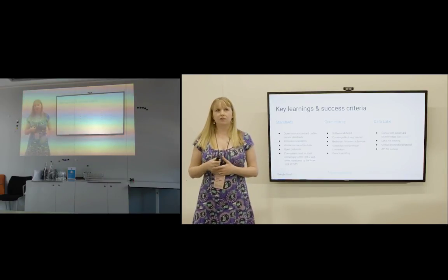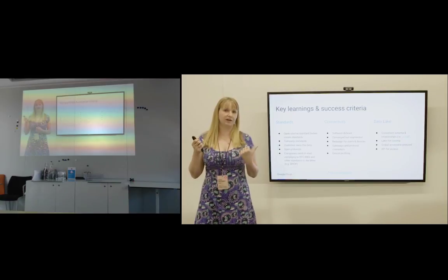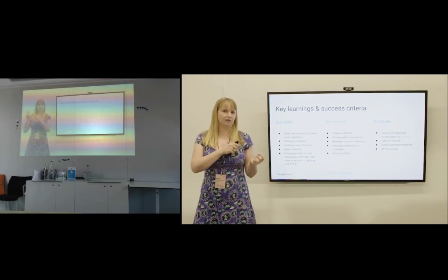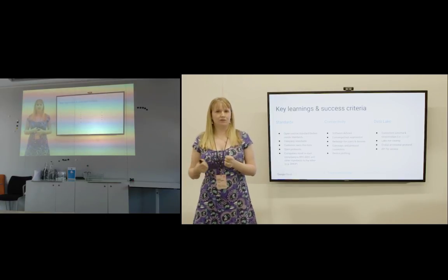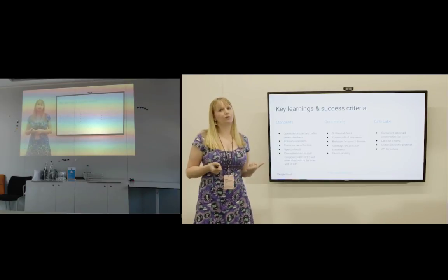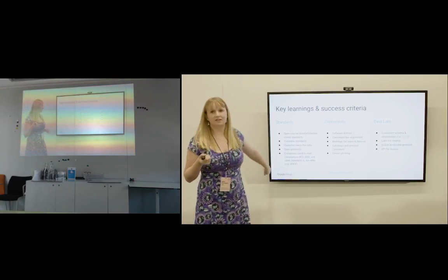And one for the device manufacturers. A lot of these devices are used to having really unreliable networks. So they've actually tweaked in a lot of cases the standards, the RFC and IEEE standards, and said, no, we're actually going to not do it that way because we can't rely on the network. But when you're moving towards enterprise and smart buildings, the network is way more reliable. An example is DHCP. A lot of the devices hold their address too long, and that's not the way they should be managed. They should be designed and built the way the standards are actually designed to do.